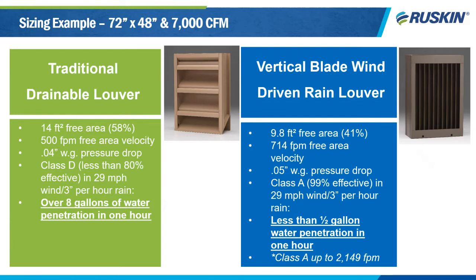So let's take the information we learned from the wind-driven rain test and put it to an example for sizing louvers. Here we're going to look at a 7,000 CFM louver. And on the left, we have a common 6-inch deep drainable blade louver that we've sized for 500 feet per minute free area velocity, making it 72 wide by 42 high. I'm sorry, 48 high. In this size, this louver provides 14 square feet of free area, or 58%, and 0.04 inches water gauge pressure drop. This is common performance for this type of louver. But from comparison testing in the basic level wind-driven rain test, we know it provides only class D rain resistance. That level of resistance allows over 8 gallons of water to come in through the louver in this test.